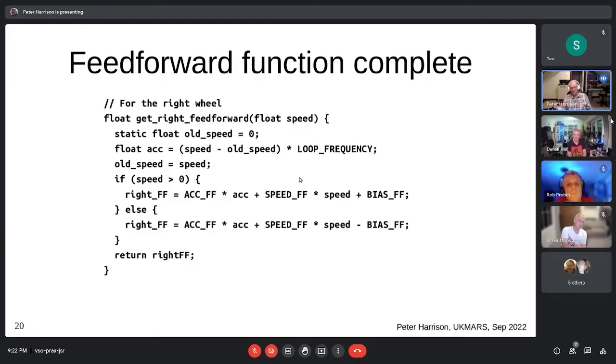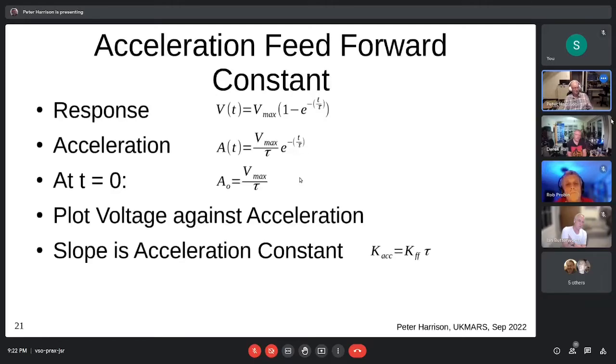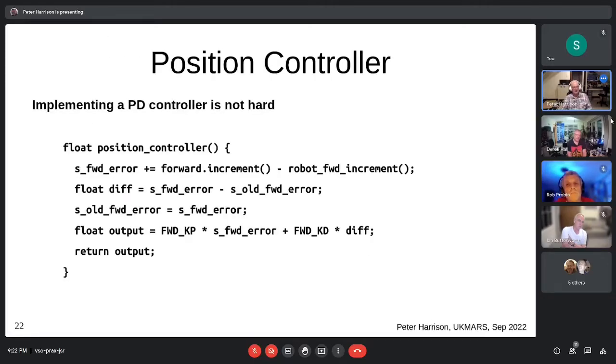So it's an extra voltage needed to drive current through the motor for acceleration and braking. So Chris, that's the answer to your question from what feels like 3 weeks ago now, about why there is a step there. It's to drive that extra current in needed to do the acceleration.